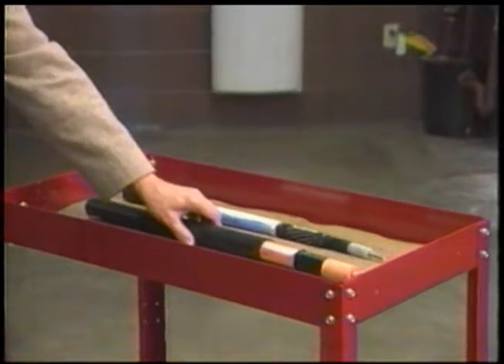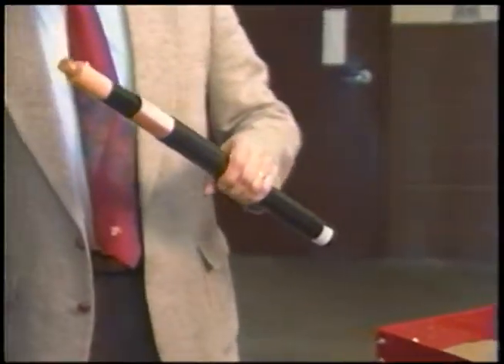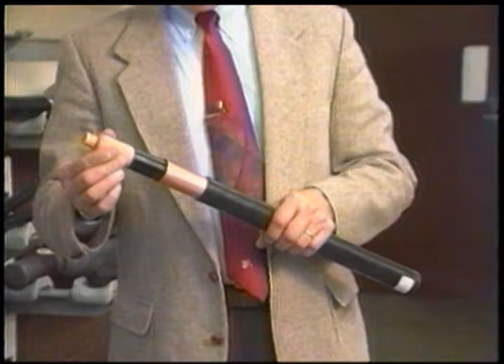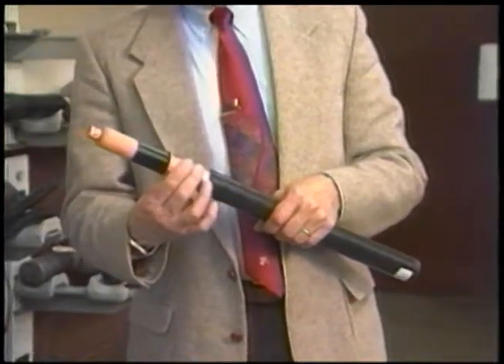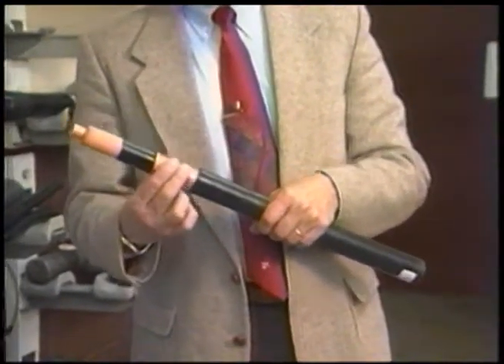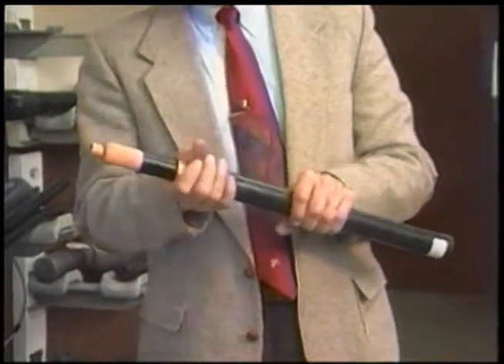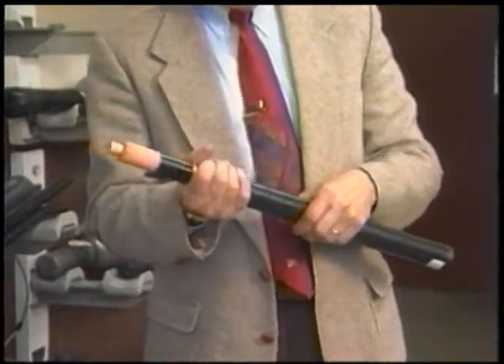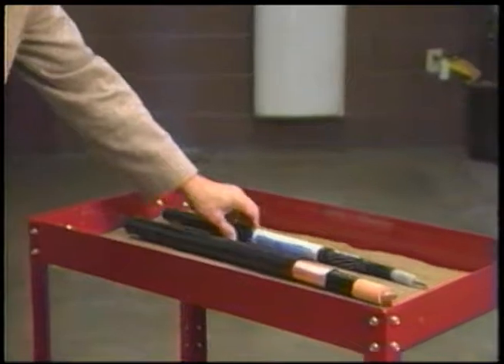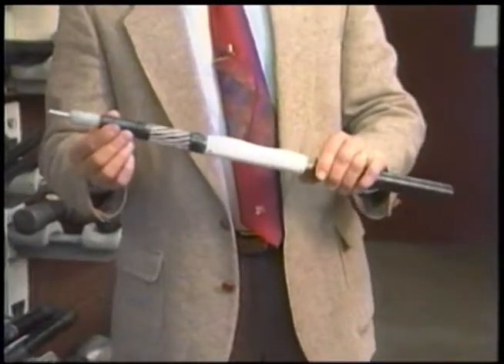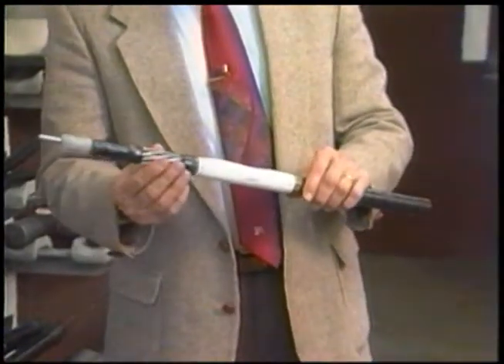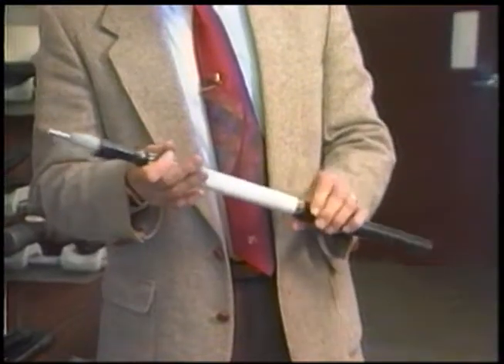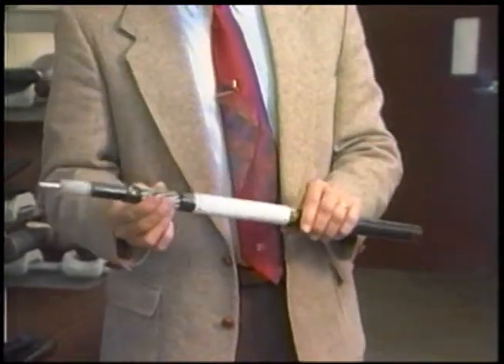We're going to replace the lead cable with this new cable, and this is a high voltage rubber cable. This too has a safety ground on it, but in this case, this is copper. Again, it wraps itself completely around the high voltage conductor. Also out in the field, we have plastic cable. This too has a safety ground that wraps itself entirely around the conductor. This is a tin copper ground.